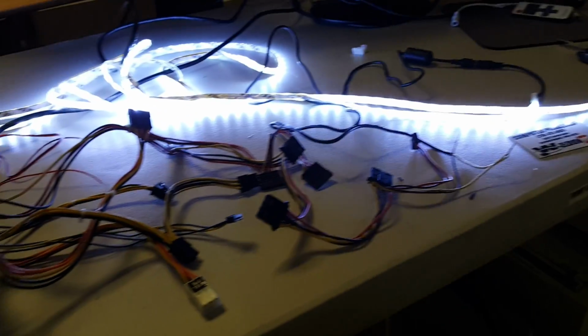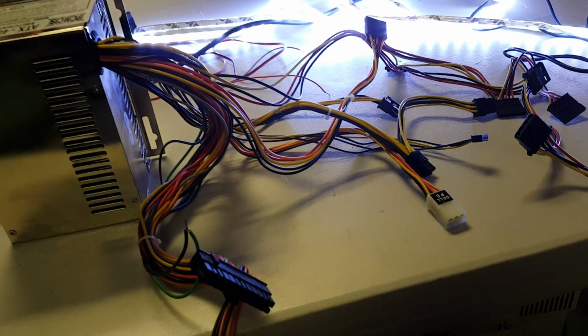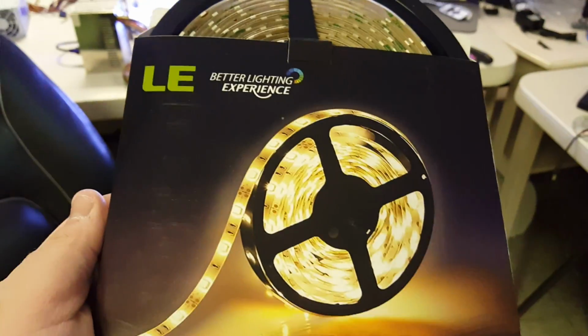You're probably asking yourself, besides being a computer nerd, why did I do this? Well, let me get to what happened. I came in over the weekend, and last night we had these lights converted to LED. Well, they stopped working because we plugged a 12 volt 3 amp power supply into three of those strips, but the strips must have overloaded the conventional power supply that ships with the LEDs that we have here. And that's these guys right here.